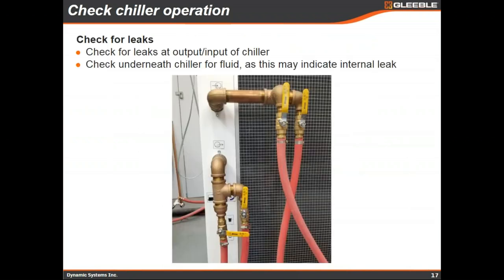Like the other units, check for leaks externally at the input and output hoses shown in the photo. Those should be fairly quick and easy to resolve. It's also possible there's an internal leak, which is usually only evident by checking underneath the chiller after some time — if glycol is pooling there, you may need to power down, remove covers, and locate the source, which may be from overfilling or excess coolant returning at one time.